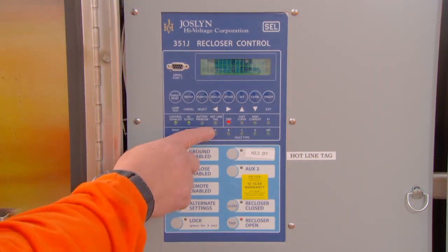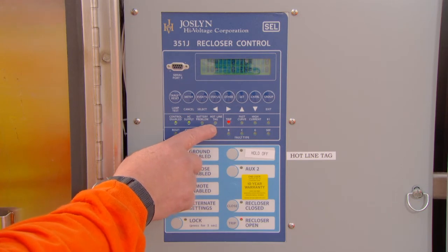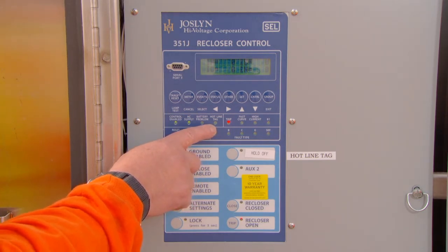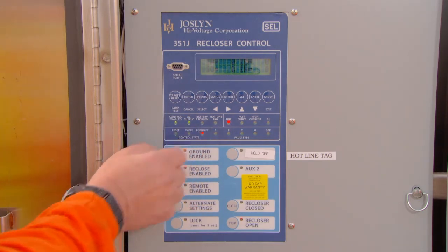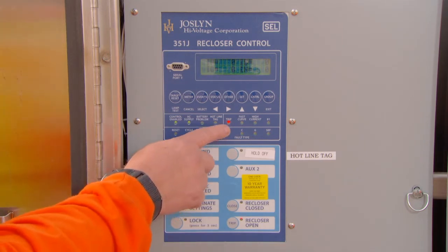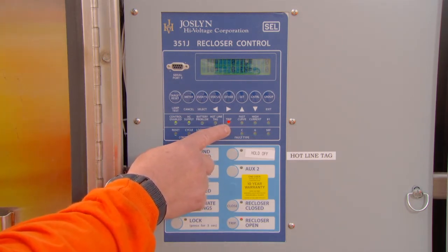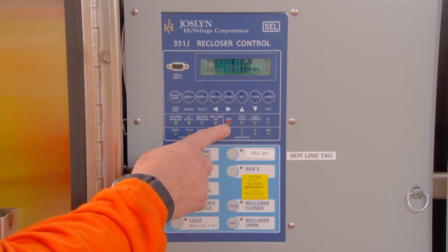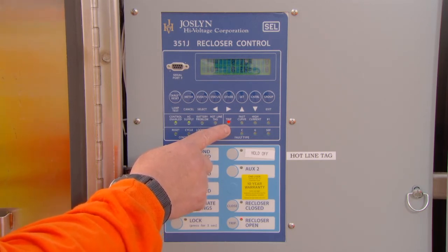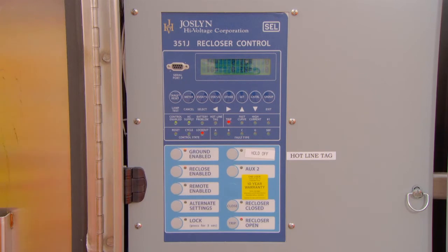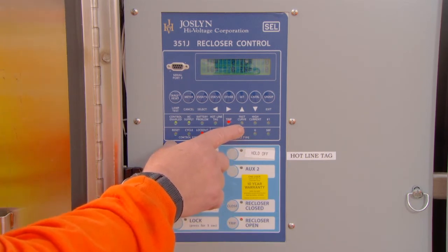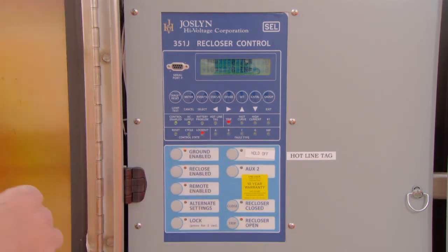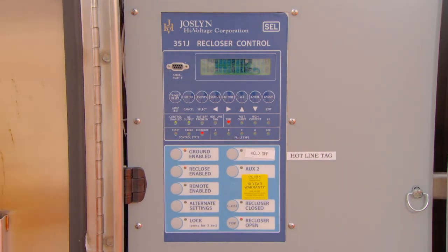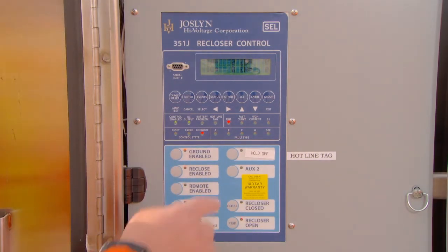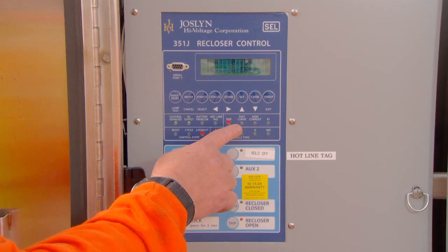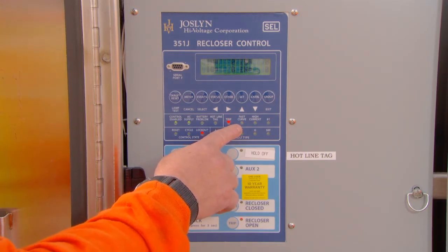The hotline tag indicator will turn red when a hotline tag, or as it is also known, a hold-off, is applied. Next, we have the trip indicator LED. If the unit has been manually tripped or tripped out automatically from a faulted condition, the trip light will illuminate red. If this unit is actually operating on a fast curve, the light will turn red. In that state, as it recloses, it will turn from red to clear.